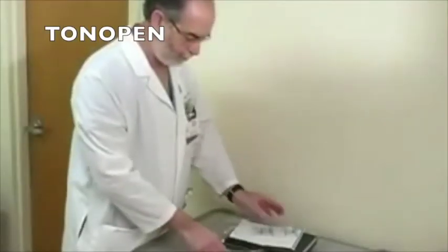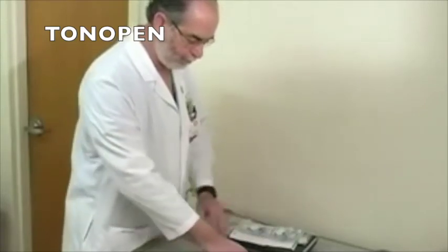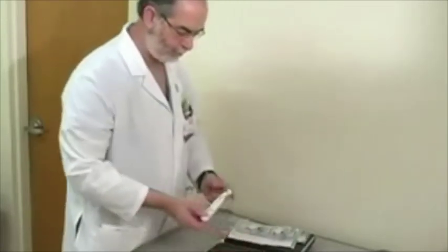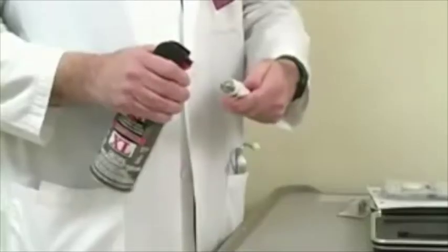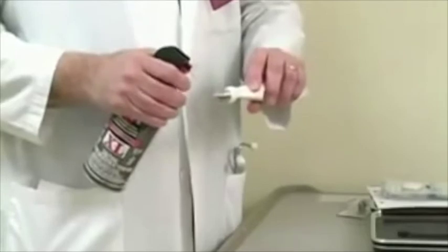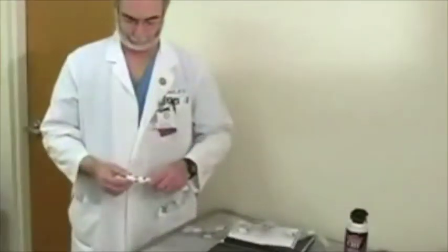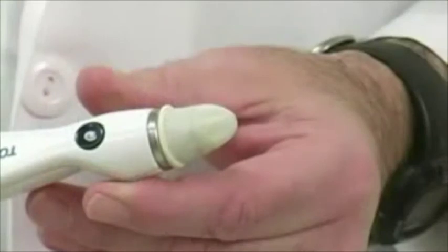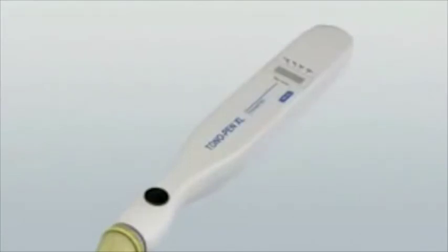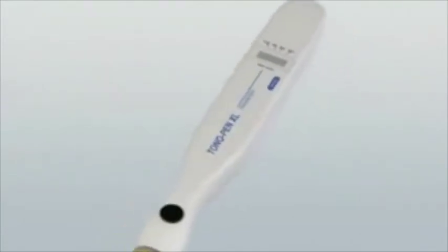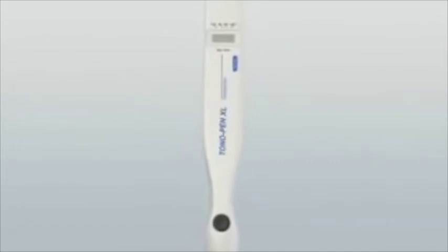You must prepare and calibrate the Tonopen device before use. Remove the Tonopen from its case and spray the probe tip with compressed gas to clean the mechanism and ensure its free movement. Place a latex cover over the probe tip. The cover should fit snugly but be free of tension. The Tonopen should be calibrated daily before use. Hold the probe vertically with the tip pointing straight down. Press and release the activation switch twice in rapid succession.